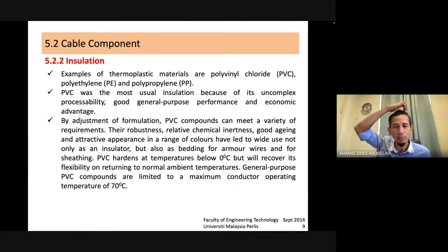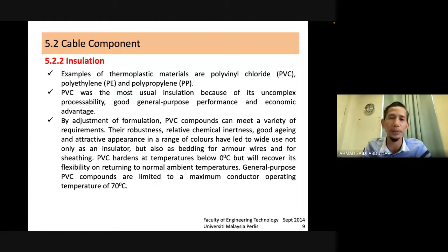So why I said important, because during the selection of cable, you need to know which ambient temperature is related during the calculation of the size of the cable nanti. So that's why you need to have this idea of what we call the maximum operating temperature of cable. This is 70 degrees. Kalau tak, if not, you will select the wrong table for selection of the cable later.